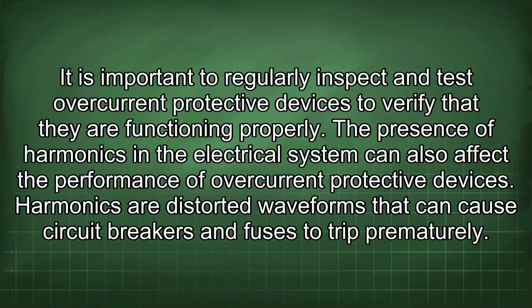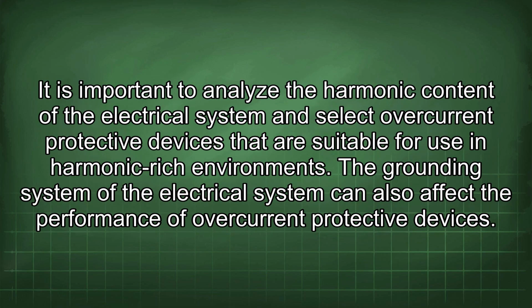The presence of harmonics in the electrical system can also affect the performance of overcurrent protective devices. Harmonics are distorted waveforms that can cause circuit breakers and fuses to trip prematurely. It is important to analyze the harmonic content of the electrical system and select overcurrent protective devices that are suitable for use in harmonic-rich environments.